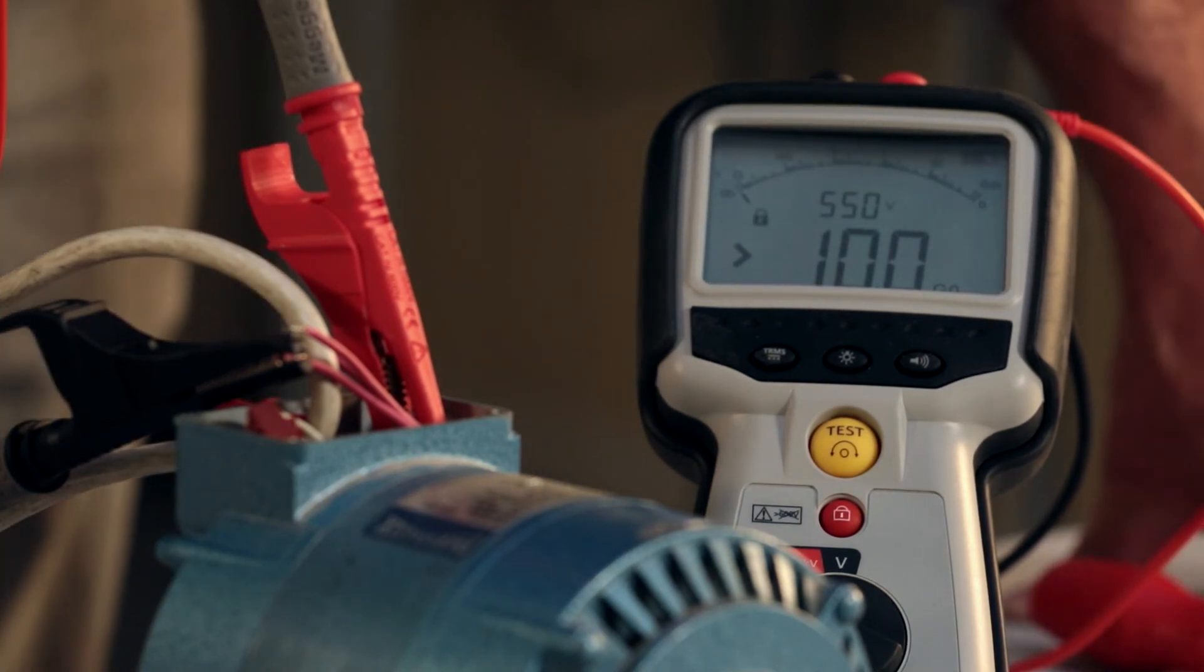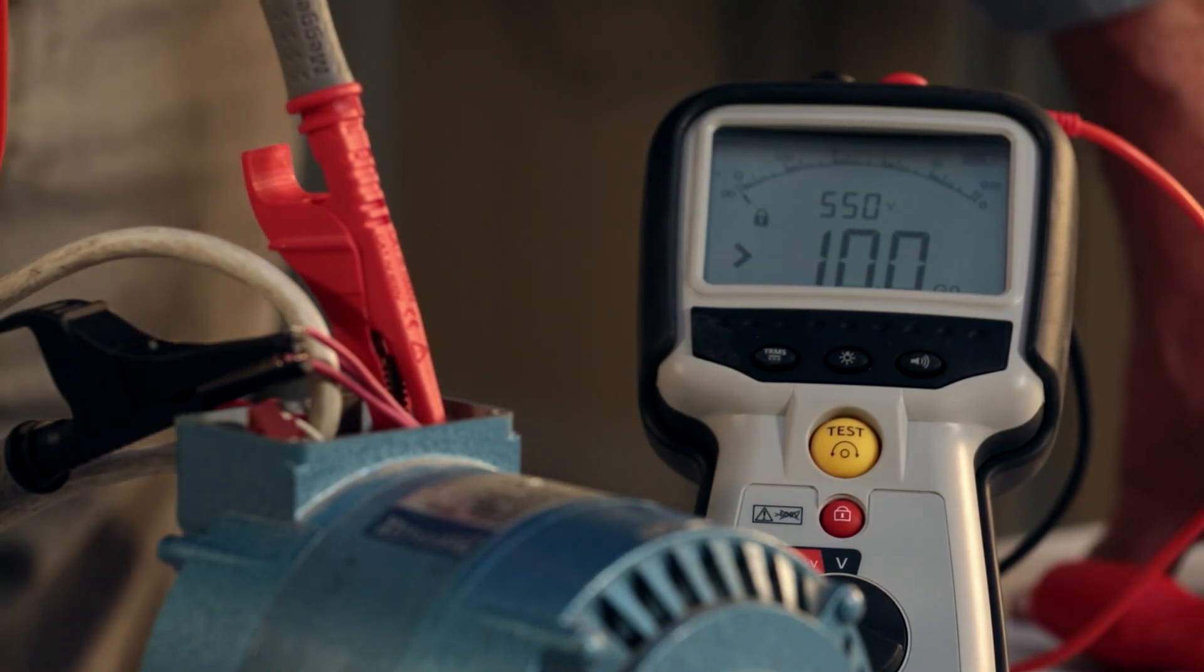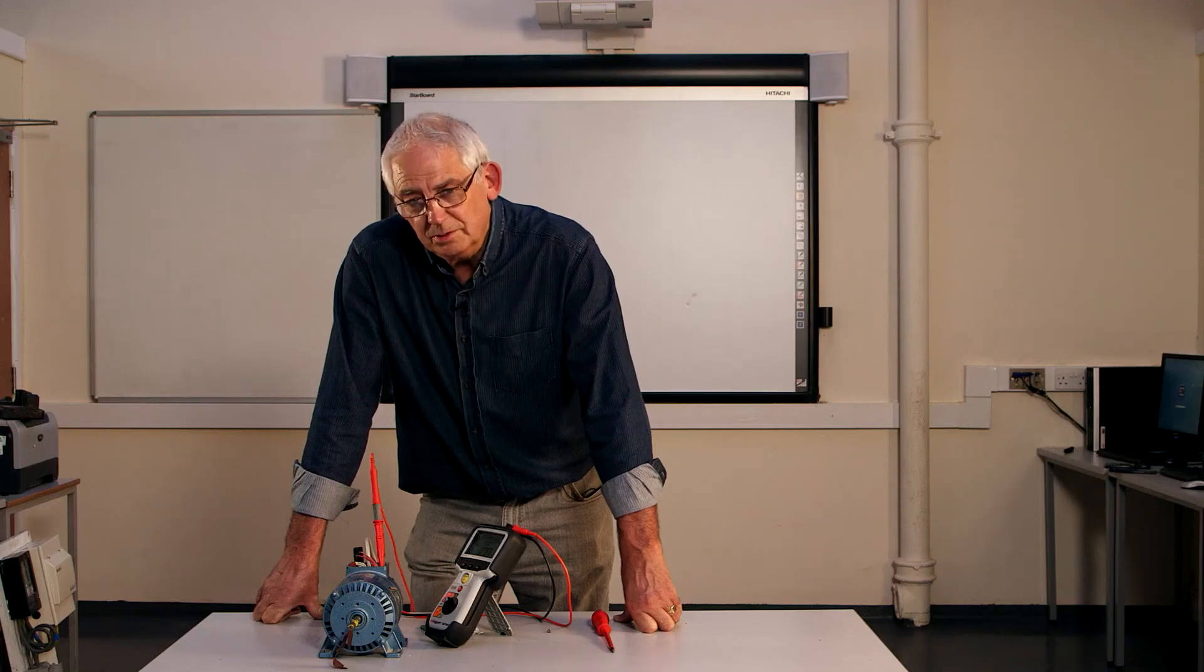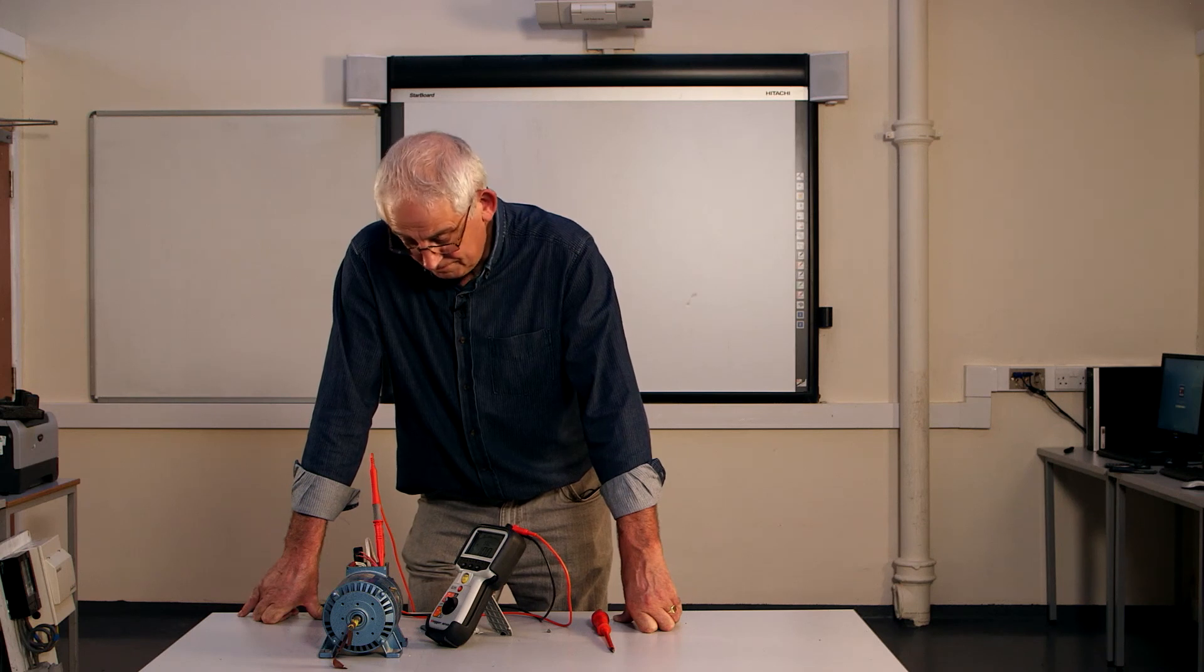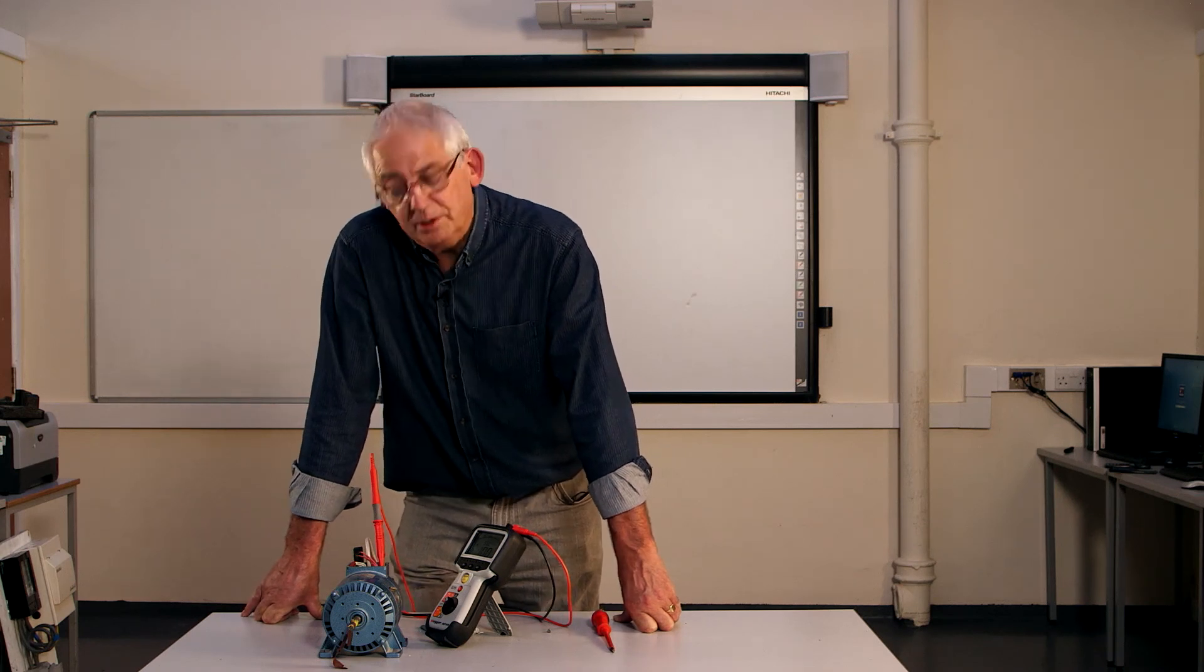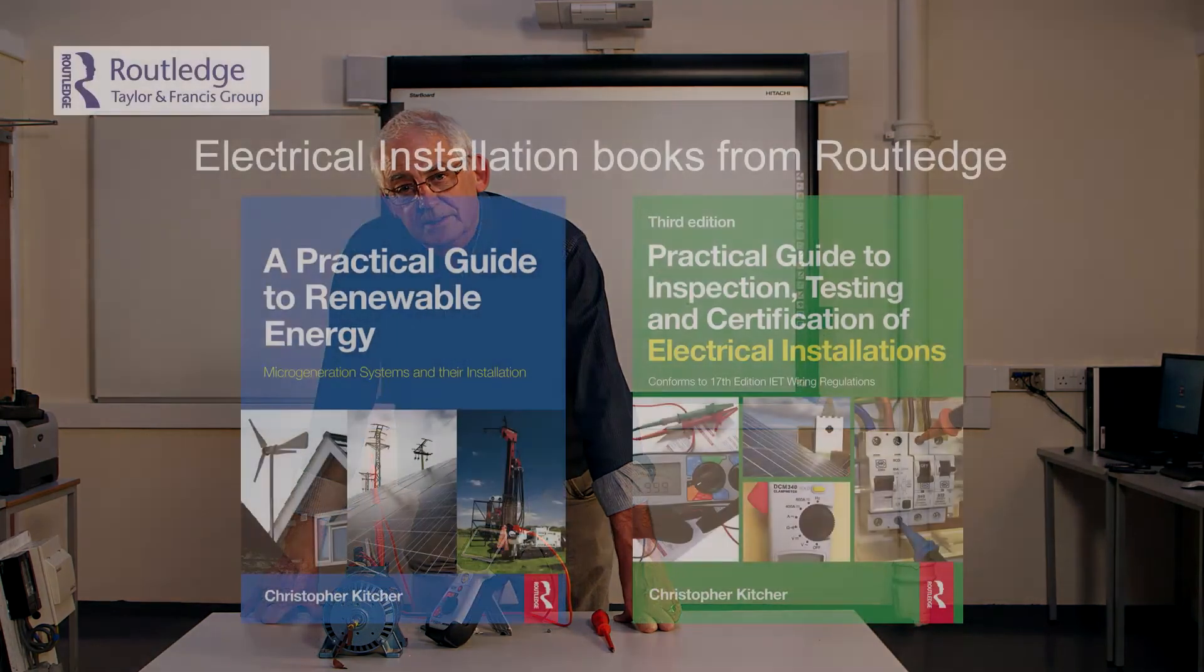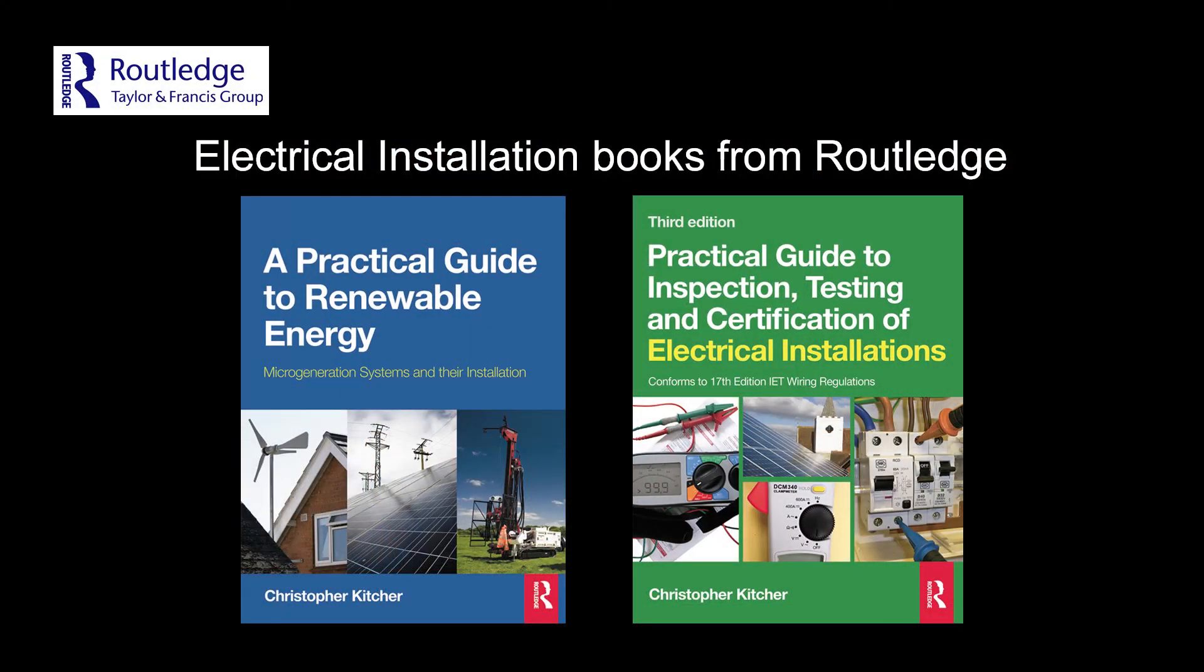But I can see straight away that actually that's a very good motor because I've got a resistance value of 10 gig ohms. So it's very, very high. That would be a good motor and you would expect that to be fit for service.